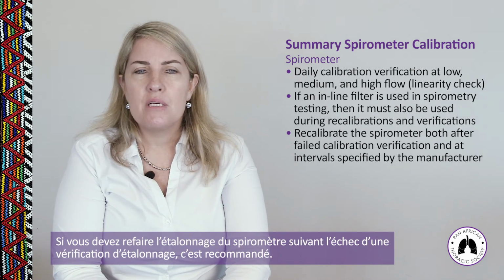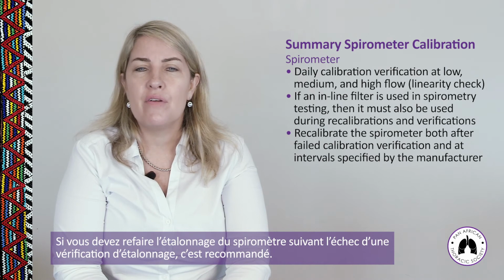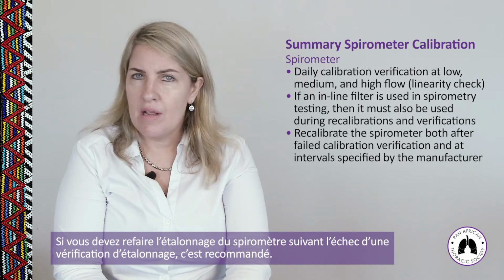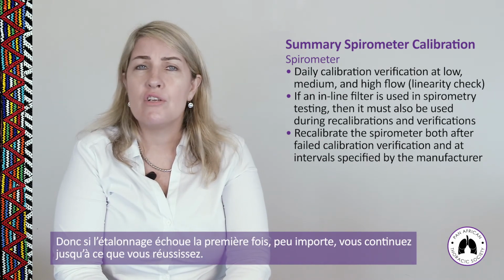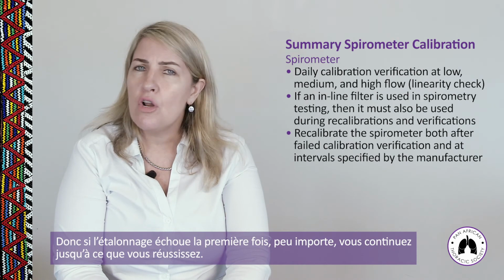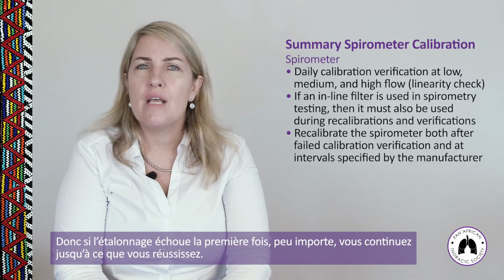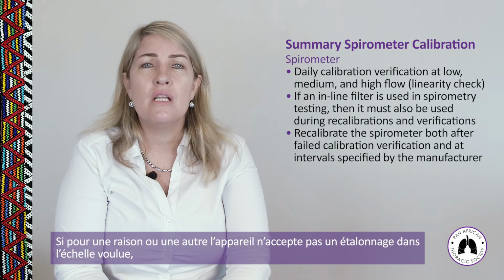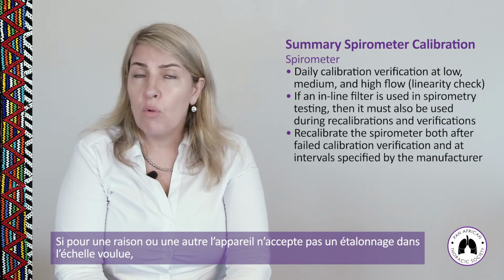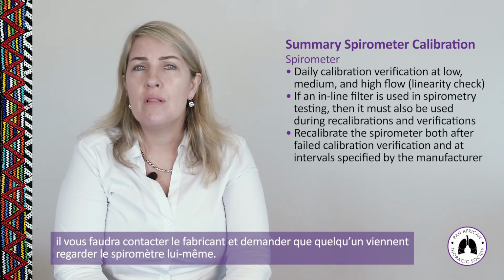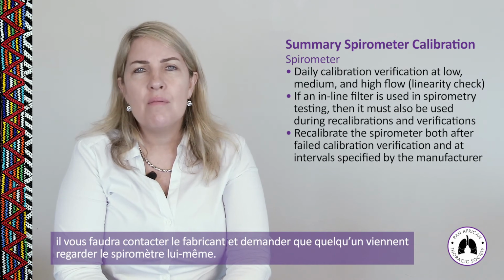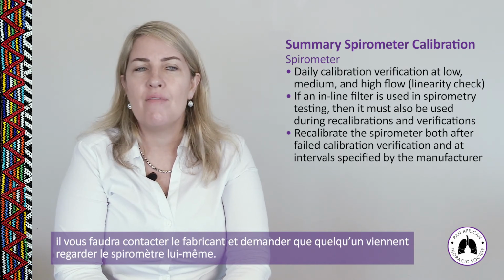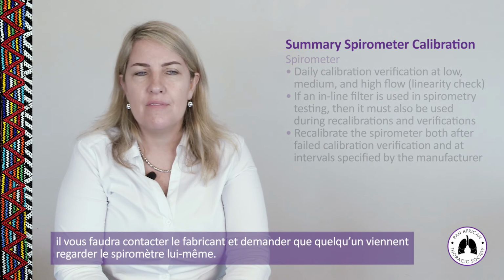Recalibration of the spirometer after a failed calibration verification is recommended. So if your calibration fails the first time, that's not a problem. You keep trying to calibrate. If for some reason the machine does not want to fall within a valid calibration, you would then have to be in touch with the manufacturer and ask someone to come and have a look at your spirometer itself.